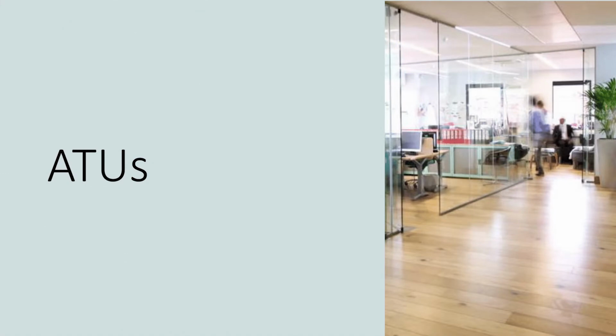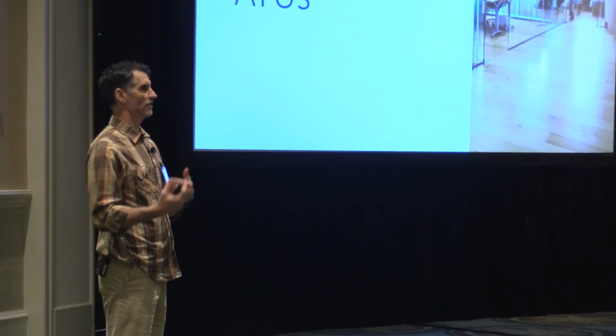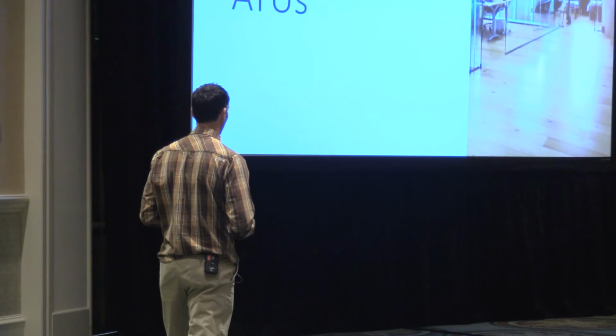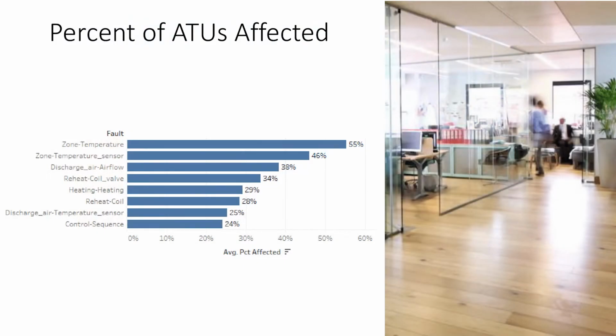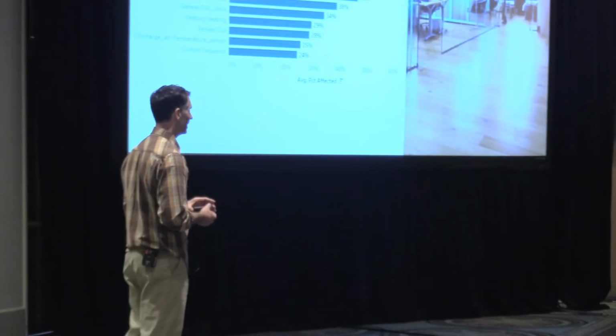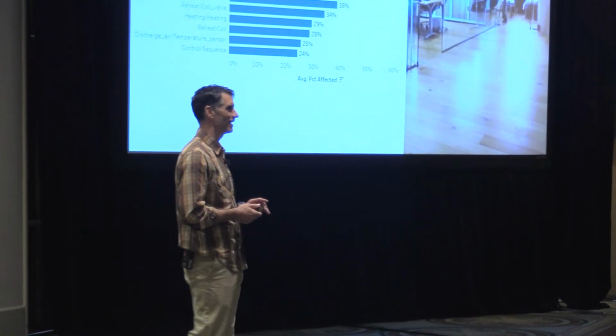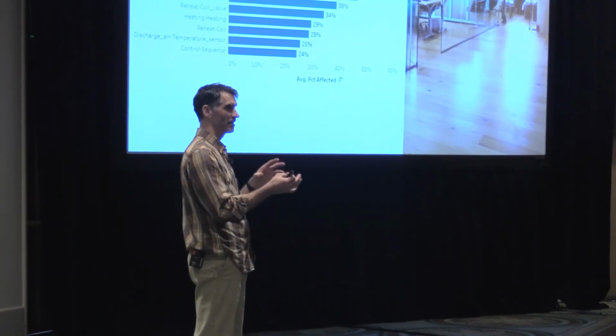Briefly on terminal units: there are fewer faults being looked for, so this is a more compressed picture. Looking at the percent of terminal units that observe a certain fault, we again have numbers over 50%, which is pretty high—zone temperature sensor issues hovering around 50% plus or minus. That seems like a lot, considering HVAC is really about maintaining zone temperature. We don't necessarily see from this chart alone whether it's an occasional issue or fairly persistent.